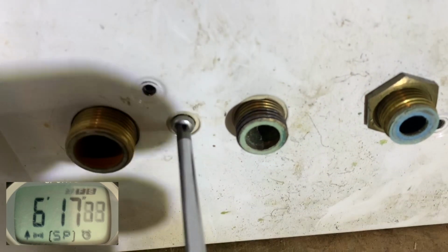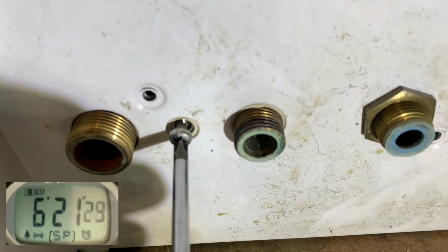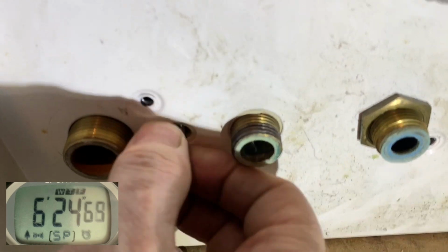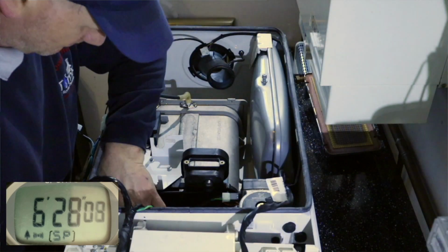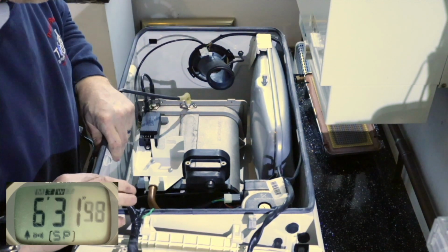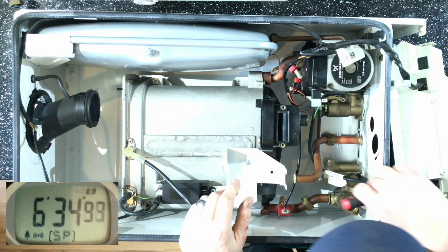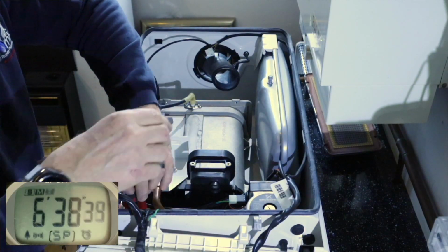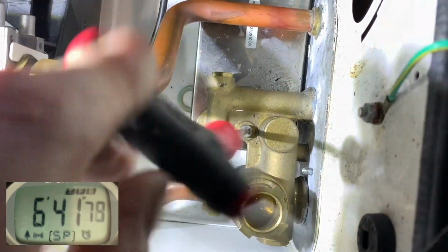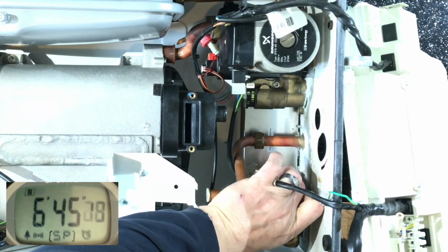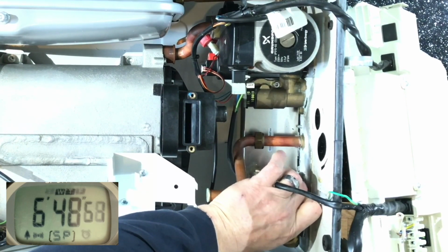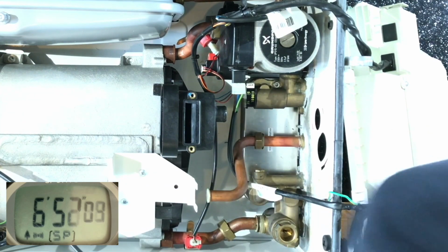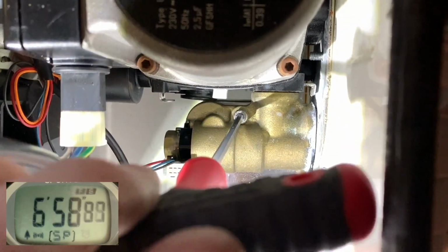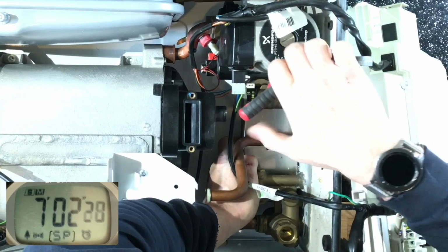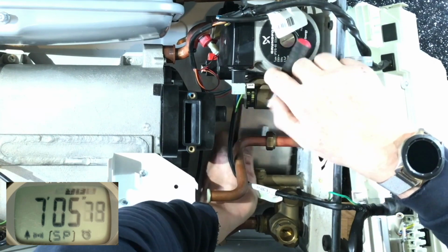So I'm just removing this left hand side hydro block. There's just a couple of screws holding the hydro block to the case, and then I should be able to move this flow pipe out of the way, and this full left hand side hydro block should come out incredibly easy. So if you had to work on this cartridge, you would remove this full left hand side hydro block to be able to get at all the components. But the plate to plate heat exchanger is connected to this by just 2 Allen screws. So I've now got the Allen key, just undoing the first Allen screw, and I'm going to remove this plate to plate heat exchanger. Now this plate to plate heat exchanger is dead easy to remove. It's just literally these 2 Allen screws, so 4mm Allen screws, dead easy to remove.